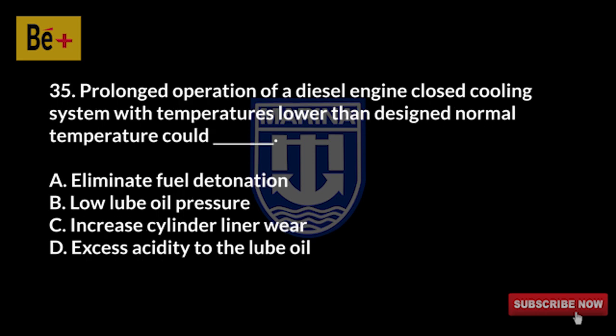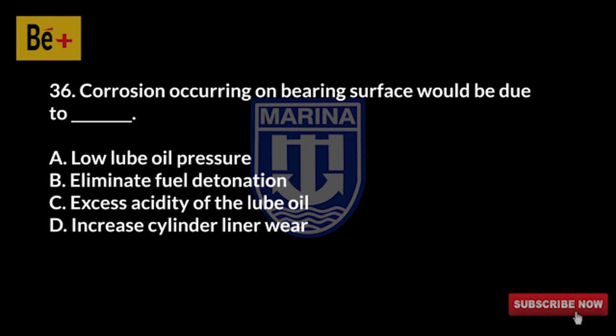Prolonged operation of a diesel engine closed cooling system with temperatures lower than the designed normal temperature could: A) eliminate fuel detonation, B) cause low lube oil pressure, C) increase cylinder liner wear, D) cause excess acidity to the lube oil. The answer is C, increase cylinder liner wear.